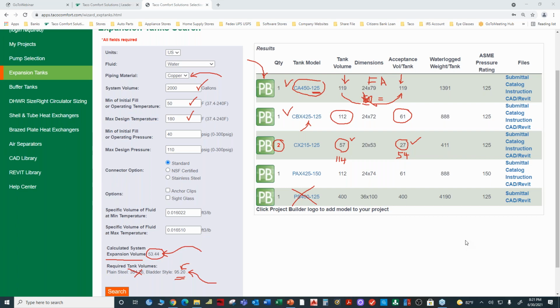Excellent. We have a question from Gene, who's in the Montana area, and he says, for a snow melt system, would you use a much lower fill temp? Well, for a snow melting system, again, it's whatever I initially fill the system with. And if my source of water is groundwater, and that's typically between 45 and 50 degrees Fahrenheit for most of North America, I would use that as my lowest temperature.